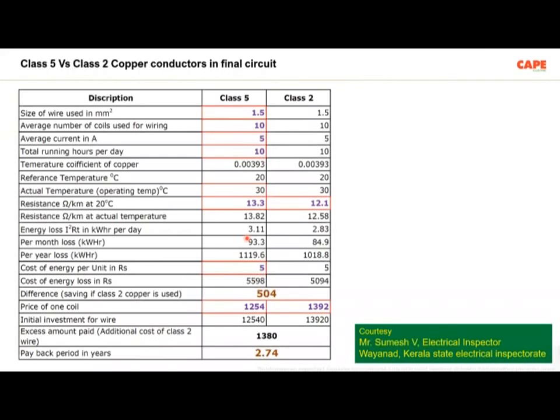Another threat which I explained during my last presentation was class 5 and class 2 conductors. In the final circuit, especially inside our houses, especially inside small scale industries, the low voltage final circuit wiring, or we use the word conduit wiring, we use copper wires in conduits, especially up to 10 square mm copper wires are recommended. Now, copper wires are available in 2 types of conductors, class 5 conductor and class 2 conductor. Class 5 conductor has a higher resistance. In comparison, class 2 has a lower resistance. The standards, be it IS standard or IEC standard or whatever, always consider a class 2 conductor for calculation of different derating figures in an electrical installation.